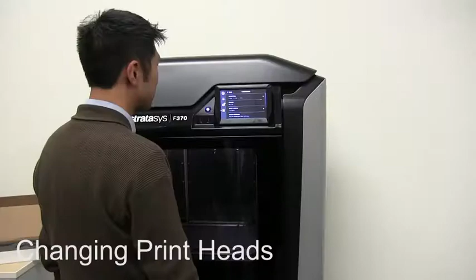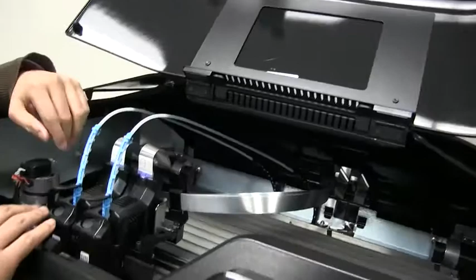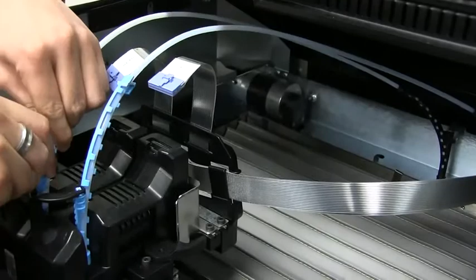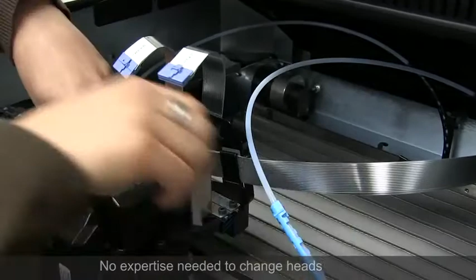To change the heads, I can access the gantry controls from the gantry and stage menu. In order to access the gantry area, I first have to open the door before I can access the heads. So we have our standard model head and our standard support head. And to release those, I move the electrical and data connection, and then remove the filament tubes. Release the lever. It releases the head.